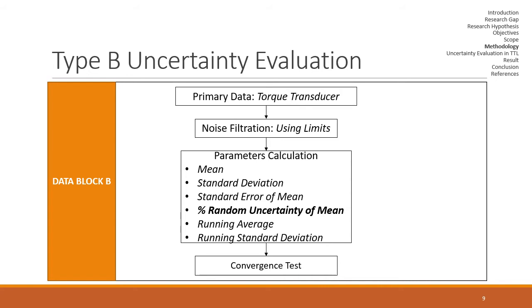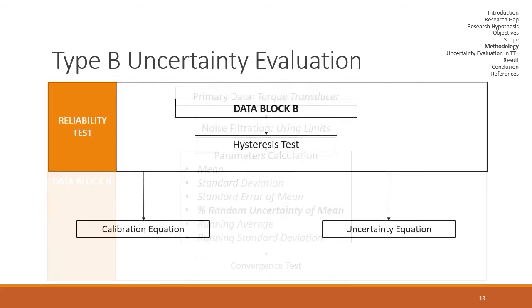So starting type B uncertainty evaluation, we have data block B, which consists of primary data received from LabVIEW program that is transmitted from torque transducer. The data transmitted from torque transducer to the LabVIEW program is in voltage form, that is processed into noise filtration using limits. After that, parameters are calculated such as mean, standard deviation, standard error of mean, percentage random uncertainty of mean, running average, running standard deviation. After that, convergence test is done. The data acquired from data block B are then processed into reliability test performing hysteresis test. Now, the data processed from reliability test are processed to calculate calibration equation and then uncertainty equation.